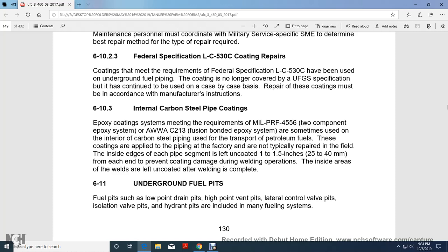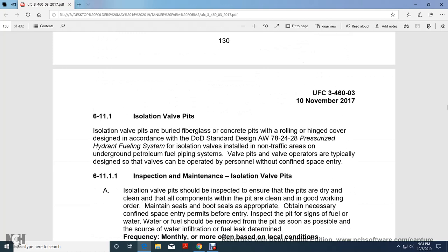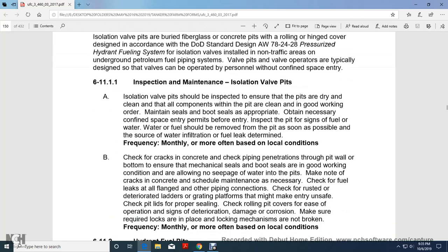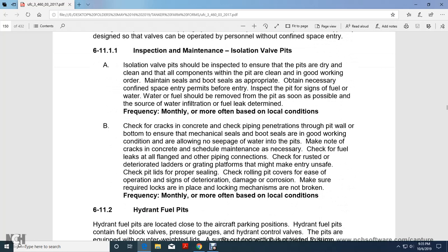6-11, underground fuel pits. Fuel pits such as low point drains, high point vent pits, lateral control valve pits, isolation valve pits, and hydrant pits are included in many fueling systems. Isolation valve pit. Isolation valve pits are made with a fiberglass or concrete pit with a rolled and hinged cover, designed according to the Department of Defense standard for the design of a pressurized hydrant fueling system. Isolation valves are installed in a non-traffic area with the underground petroleum fuel piping. Valve pits and valve operators are typically designed so the valves can be operated by personnel without confined space entry. Inspection and maintenance of isolation valve pits.